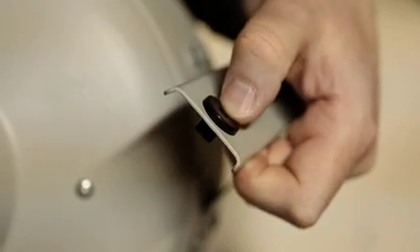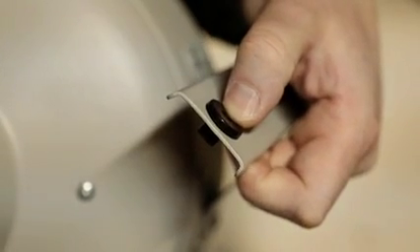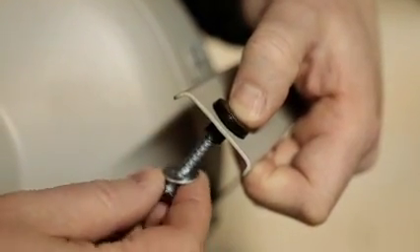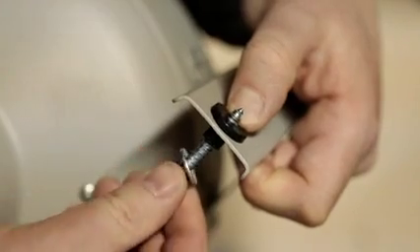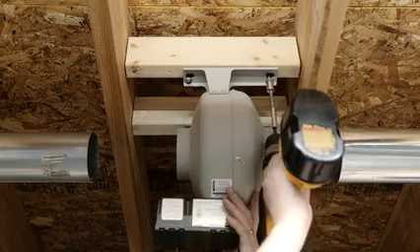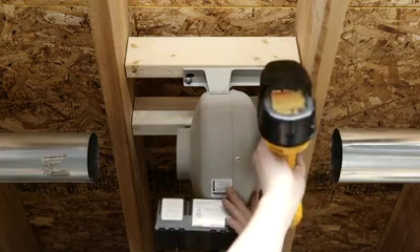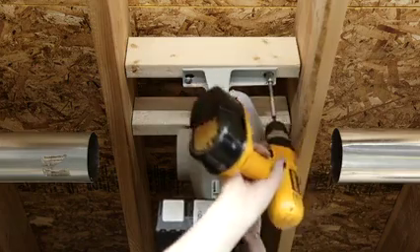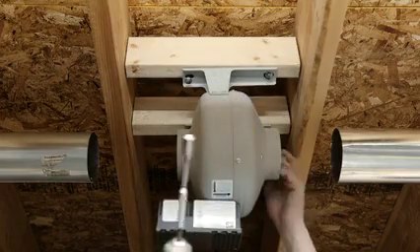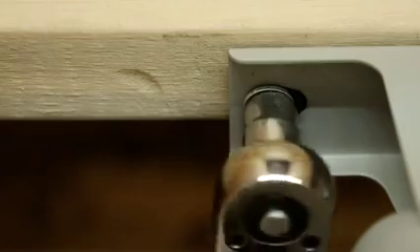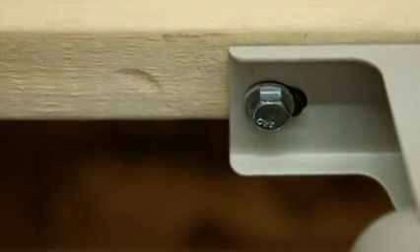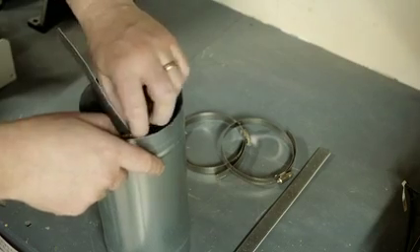Next, place each of the provided rubber grommets on the underside of the mounting bracket followed by the washers and lag bolts. Use a 7-16th inch wrench or socket to secure all four lag bolts. As the bolts are tightened, the washer will squeeze the rubber grommet onto the bracket providing vibration isolation from the framing.